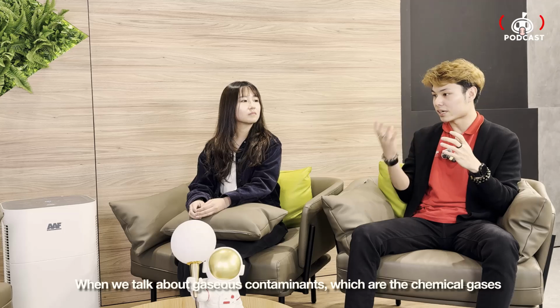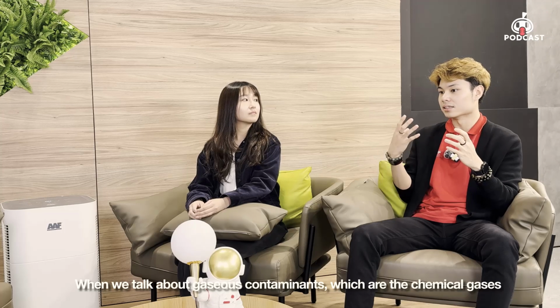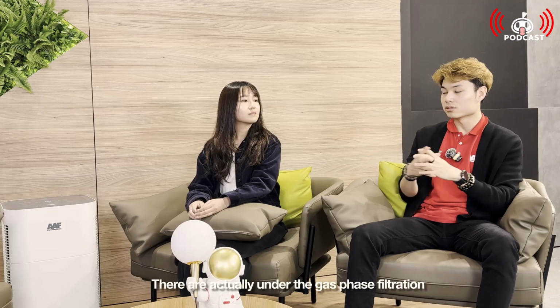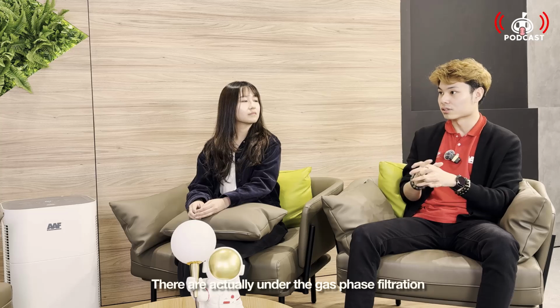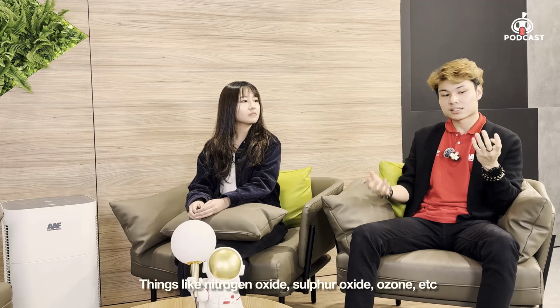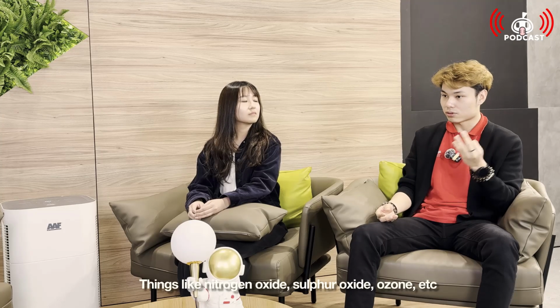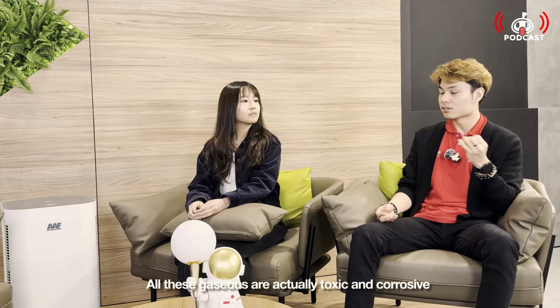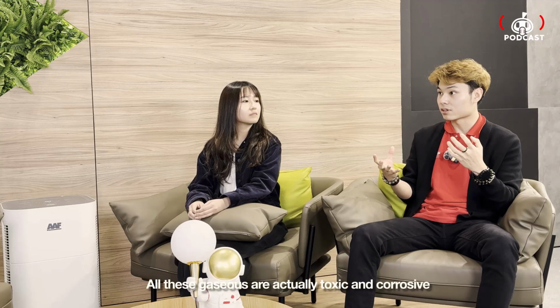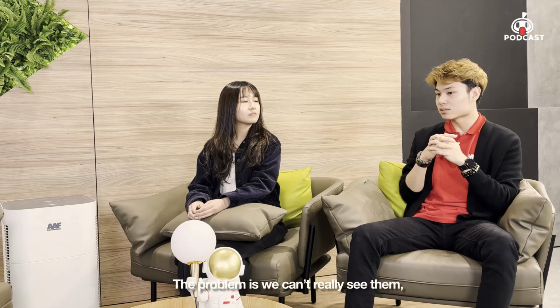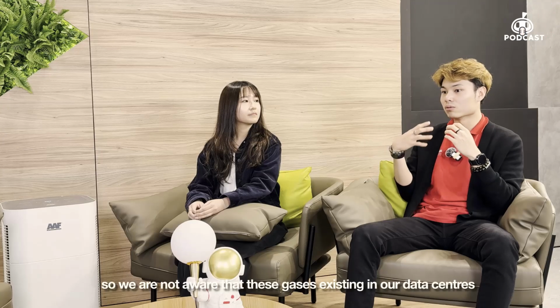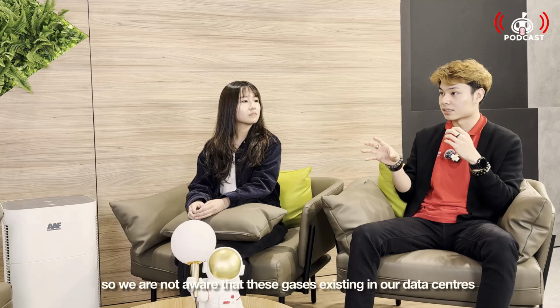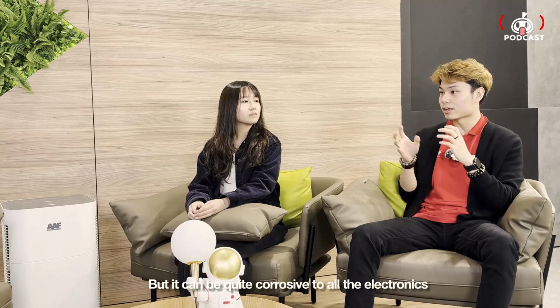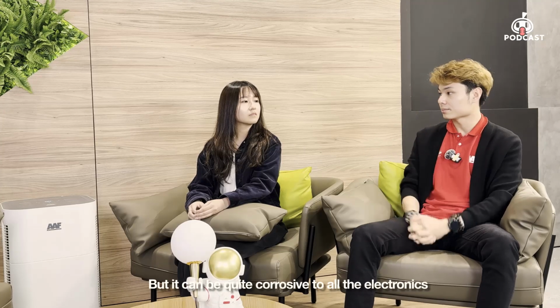When we talk about gaseous contaminants, which are the chemical gases, that is actually under gas phase filtration. Okay. So things like nitrogen oxide, sulfur oxide, ozone, etc. All these gases are actually toxic and corrosive. But the problem is we can't really see them, so we are not aware of these gases existing in our data centers. But they can be quite corrosive to all the electronics.